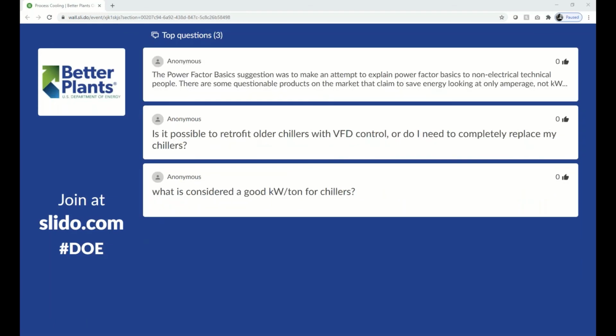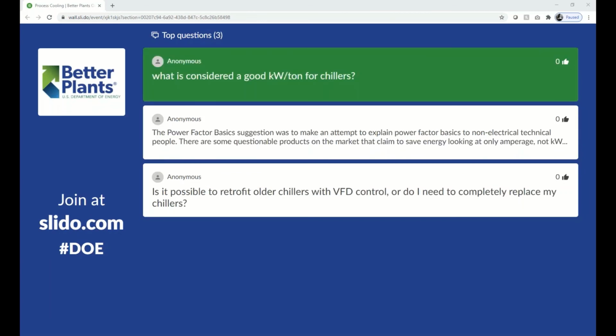Fantastic. One or two more questions, Wei. What is a good kilowatt per ton for chillers? Actually, 90.1 has a standard, that's a good number that we can use. For kW per ton, we have the design kW per ton for the design conditions, and I would think probably 0.7 or 0.6 should be pretty good.